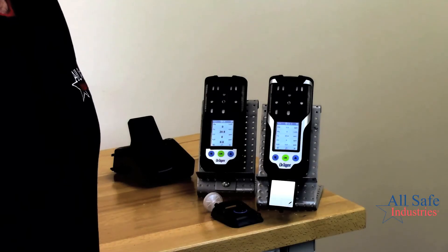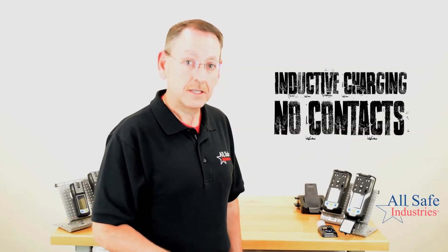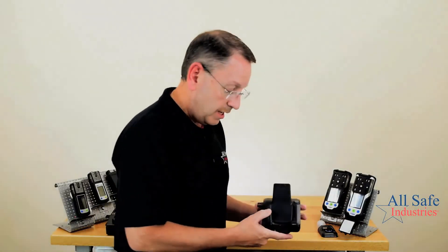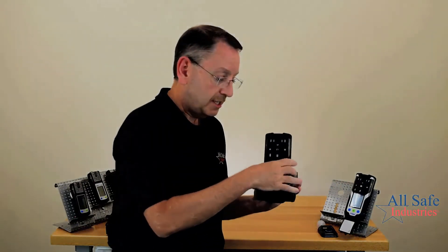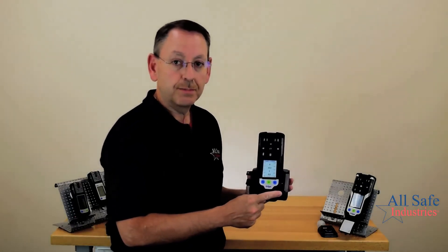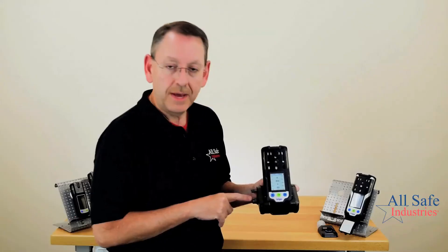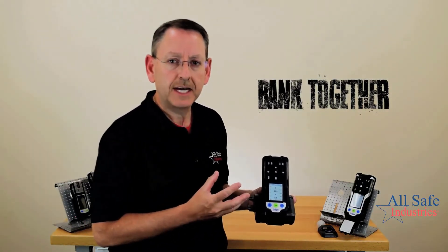Another new feature Draeger added to the X-am 3500 and the X-am 8000 is inductive charging. No longer do you have contacts on the back of the instrument that could become corroded, or pins on the charger that could get broken or bent. This charger has no contact points — it charges inductively. You just take the instrument, set it in the cradle, and a light shows you it's charging; when it turns green, your battery is fully charged. If you put the instrument in the cradle while it's running, the cradle will automatically power down the meter to enter charging mode. You can also bank multiple chargers together to create a complete system for your entire fleet.